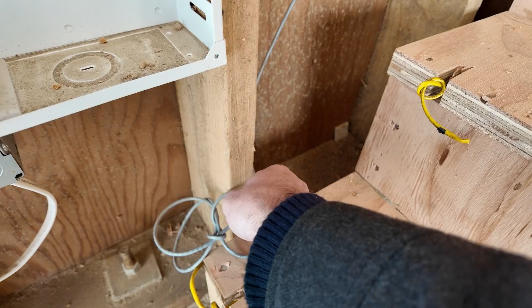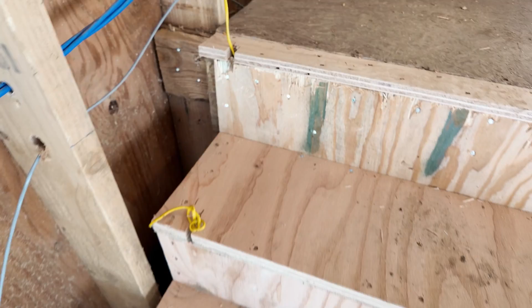Also of note down here, we've got power for the stairs. This is a 3-conductor wire for the motion sensor, which will live embedded into the wall right on this first step. And these are low voltage wires for the LED strips that will go under the tread - each step has a little wire connected for the understair lighting.